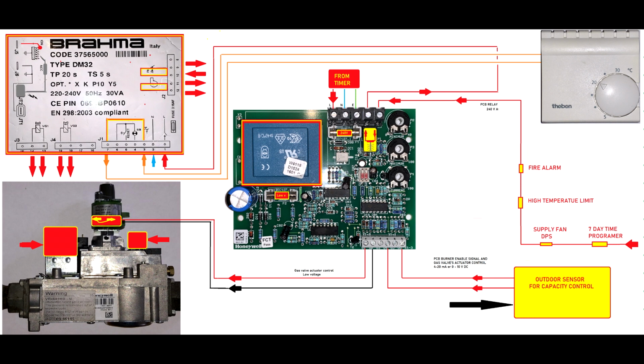So if the probe which is outside demands heating because outside is too cold, then it is easy. You will enable that relay, and you will enable the control capacity of the printed circuit board. It's easy. You will act just like a programmable logic controller. You will have the capability to increase or decrease the voltage, or increase or decrease the amps as per the temperature outside, because you might use a thermoresistor with a repeater or with something that can convert that signal into 0 to 10 volts or 4 to 20 milliamps.